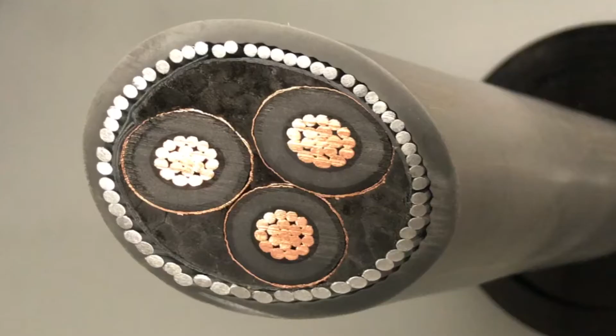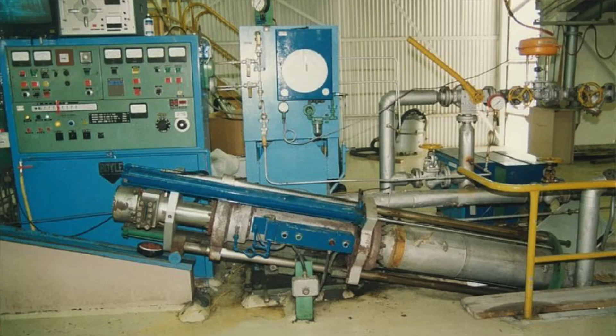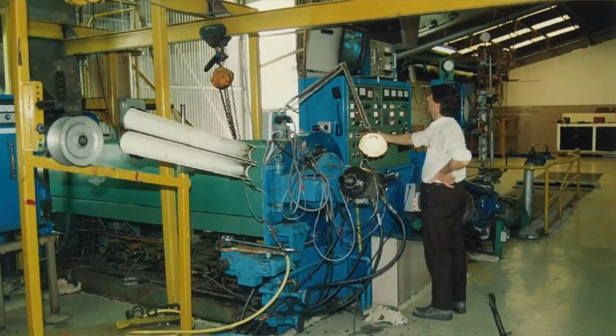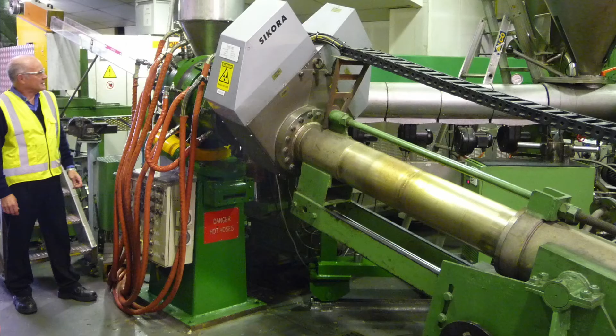In 1973 they started to develop extruded semicons, to remove the tape screens. That gave the biggest increase in life of the cable and reduced the number of cable faults. In 1990, when we upgraded our steam line, we moved to dry cure triple extrusion, once again to eliminate moisture within the insulation. At the same time, we introduced the tree retardant compound. So for us, in performance and long life, that was a fairly big step forward.